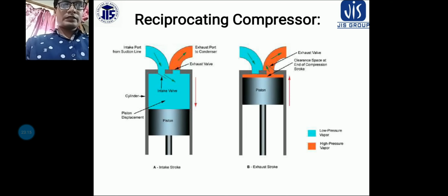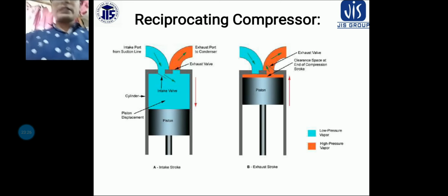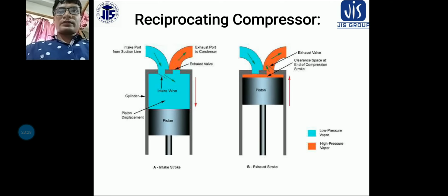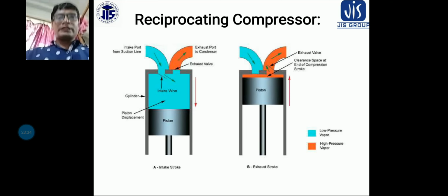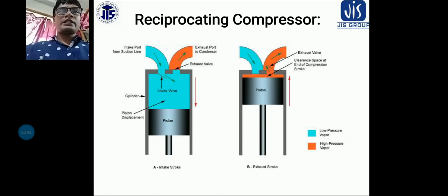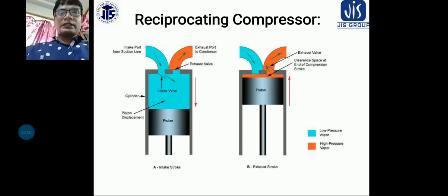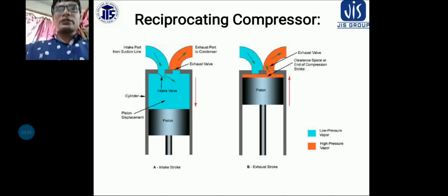volumetric efficiency. The volumetric efficiency of a better compressor is 70 to 80%. Based on the volumetric efficiency we can say how much volume of refrigerant is entering, that means what is the suction volume, or actually how much amount of refrigerant is entering by the swept volume. Okay, so actual volume by swept volume is the volumetric efficiency. Okay, so this is all about the terminology.